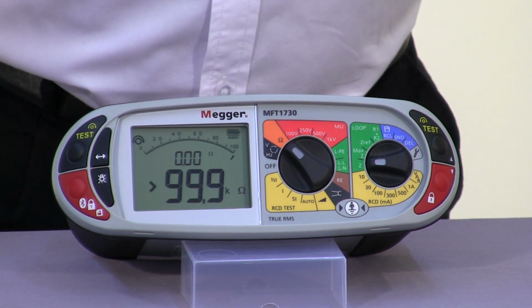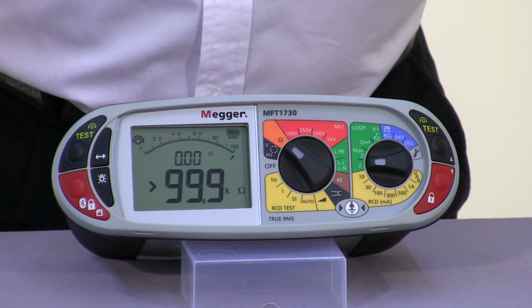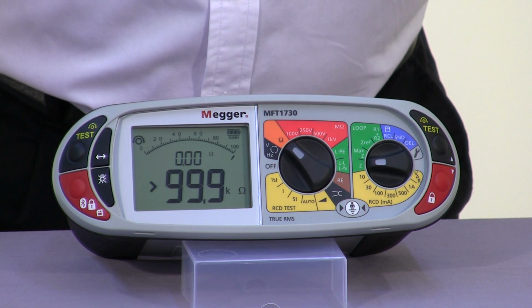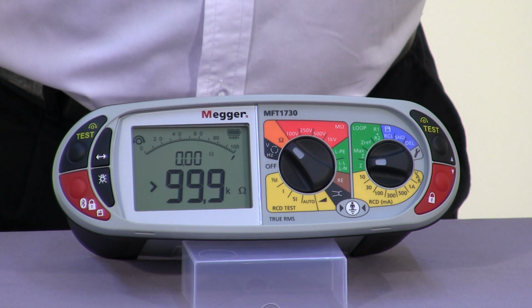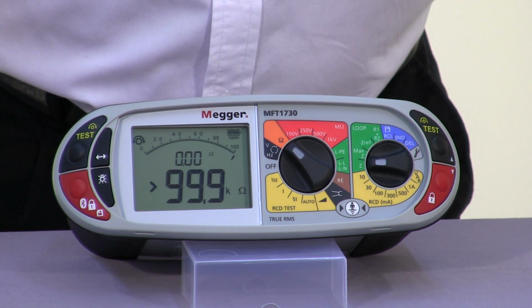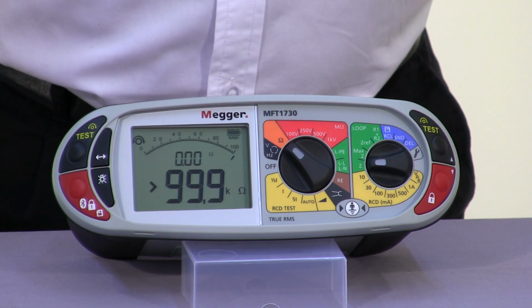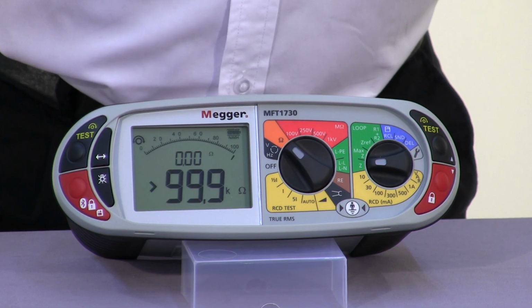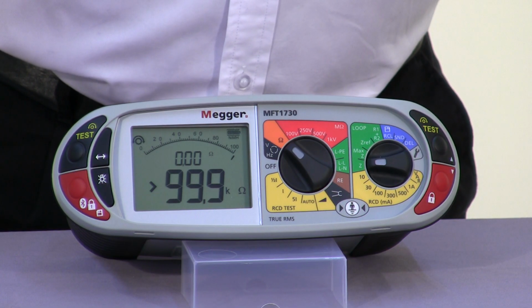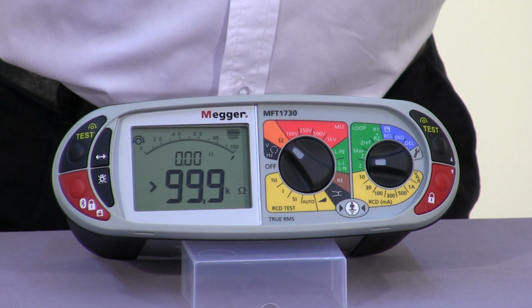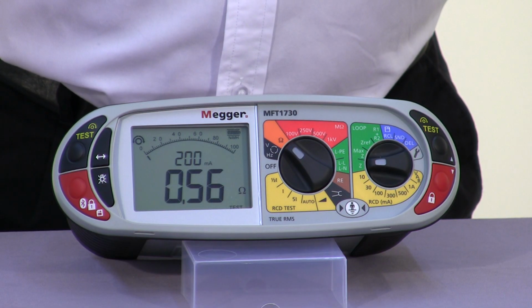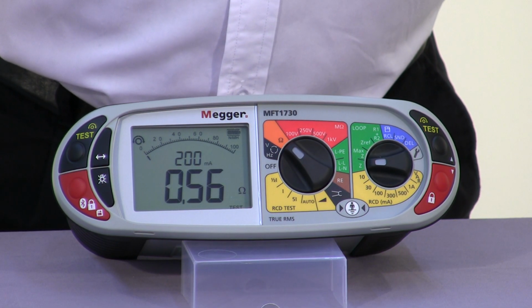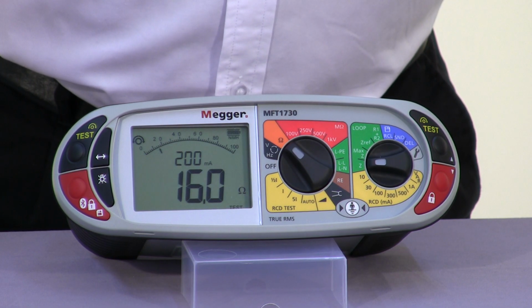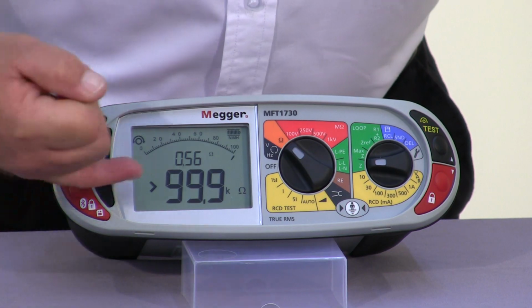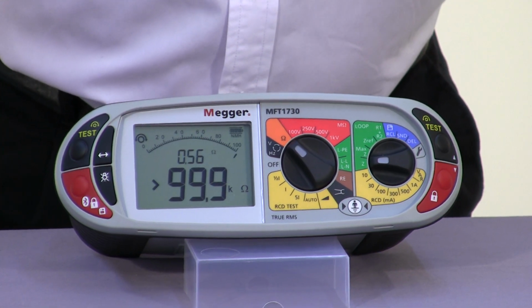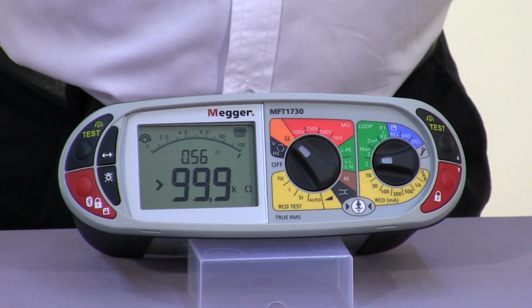Okay, so having nulled out the leads, what we'll do now is take a straightforward continuity measurement. Now, one of the nice features on the 1700 series is that once you've got a stable reading, you get an audible indication. So if you were testing in the top of a distribution board, you wouldn't need to be concentrating on what the meter is doing, as you get a nice beep to indicate that the test has been completed. So when we apply our known value, we get the audible beep. We can remove our probes from the test circuit, and as you can see, the reading has now been transferred and is displayed on the upper of the two parameter display.